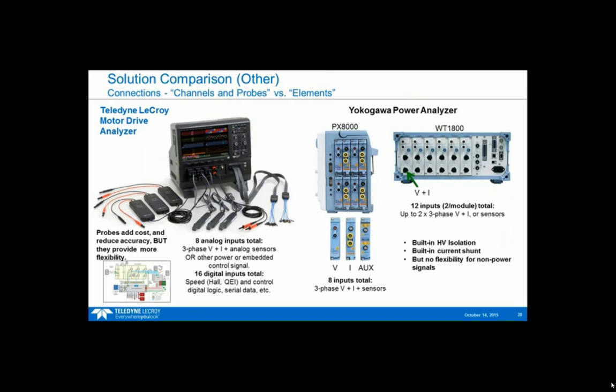If you have a current output from a conventional turns ratio CT, we sell a device called a CA10, which includes a shunt resistor you can build in, turning that current output into a shunt resistor voltage output, and then scale that as well. We have the ability within the channel menu to change the units from volts to amps and scale it linearly. So yeah, the short answer is yes, you can do all those things. You have complete capability within the instrument, and we're compatible with Rogowski coils, Pearson CTs, DanaSense, DanPhysic, LEM DanPhysic, conventional turns ratio CTs - just about anything.